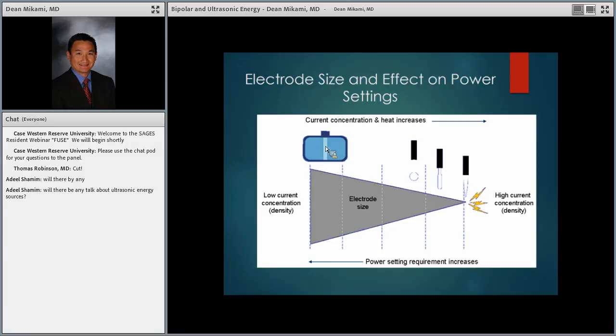The nice thing about technology today is that you can see on this pad, it's a split pad. It's got 50% on the left, or maybe 45% on the left, 45% on the right, and they're striped down the middle. So what that is for is the dispersive electrode and the ESU is trying to figure out how much current is coming back from the active electrode. And if I get 45% here and 45% there, the machine stays on. But if the pad starts to peel off and I get 45% here and only 10% here, then the machine will shut off.